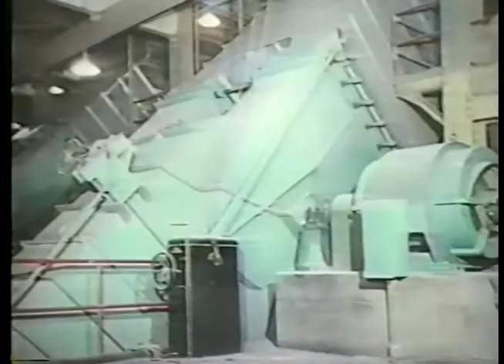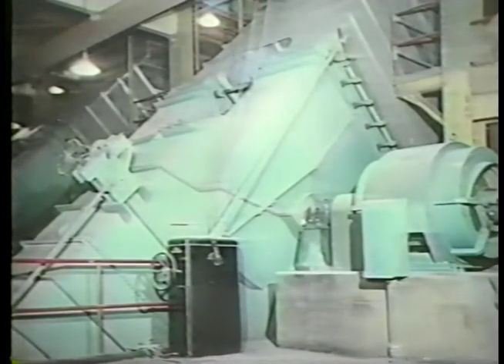With this system, the operator first starts the induced draft fans. The induced draft fans draw air out of the boiler and establish a slight negative pressure throughout the furnace area. Once the induced draft fans are in operation, the next step is to start the forced draft fans to increase the amount of airflow through the boiler. On boilers that operate under a positive pressure, it is only necessary to start the forced draft fans, since these systems do not have induced draft fans.